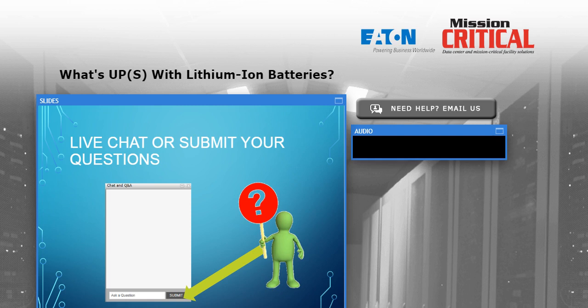I can also monitor the UPS, which is receiving signals from the battery system, and use the same monitoring, Modbus or SNMP or whatever that I would use to monitor my UPS system on the network, and I would get battery-related alarms and conditions and status via my connection to the UPS. So there's lots of choices.